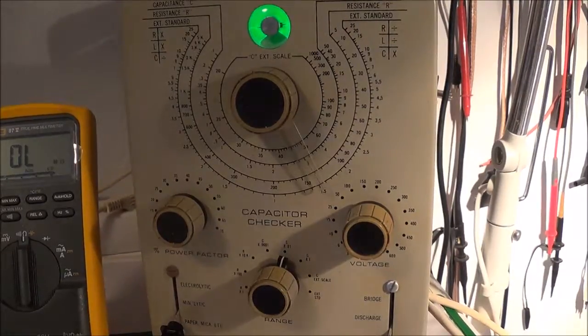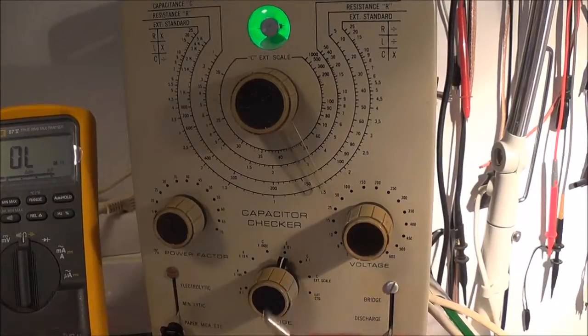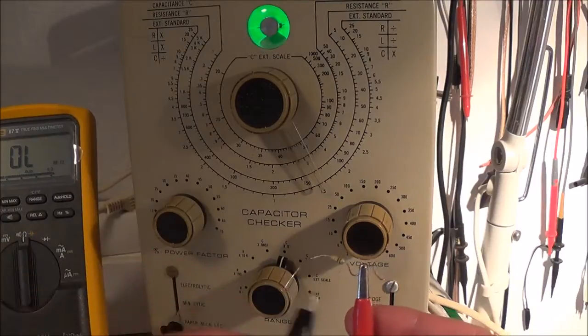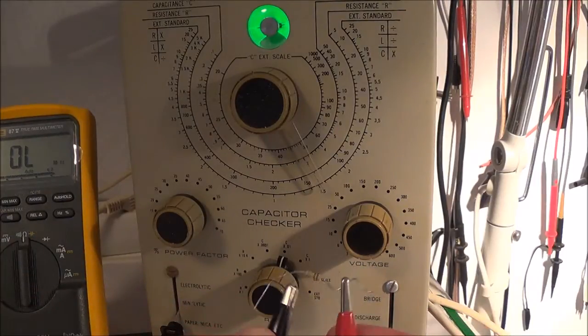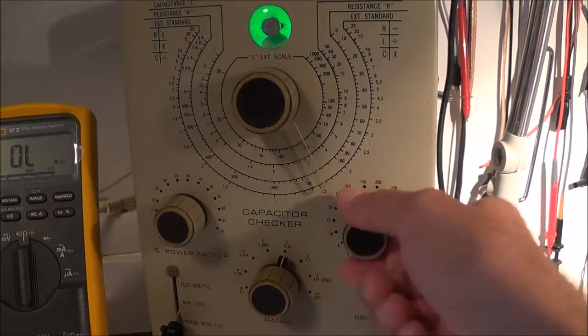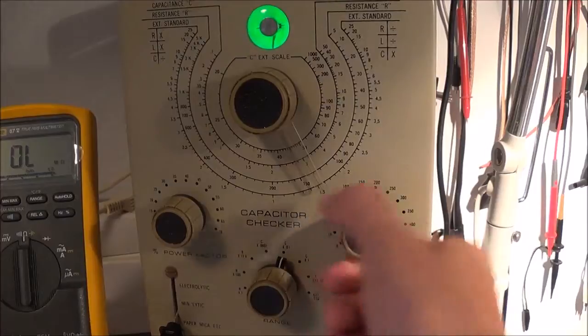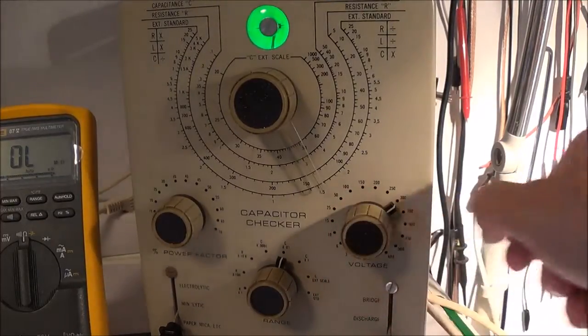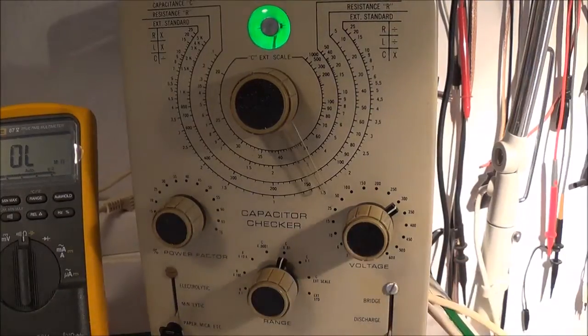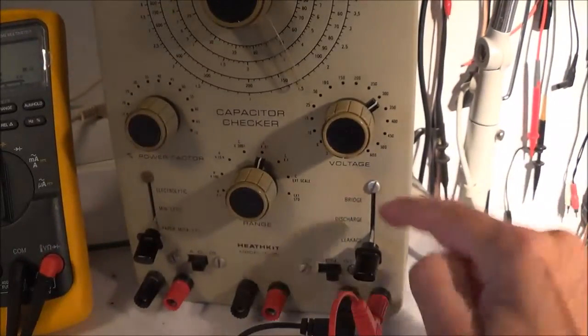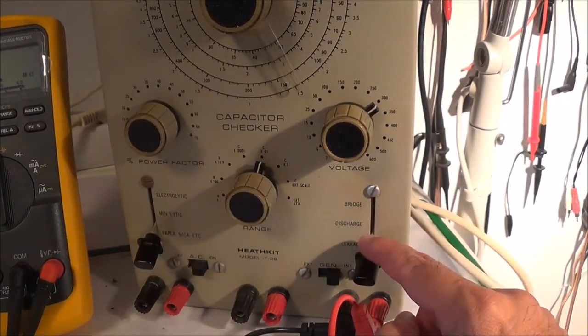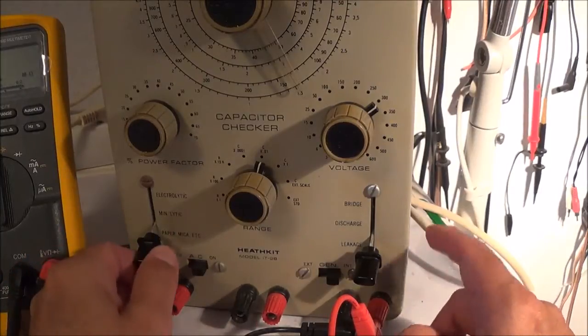And then connect this across the test terminals. Thereafter, I have to turn the voltage up to 300. And of course, this bridge discharge leakage switch has to be in the leakage position.